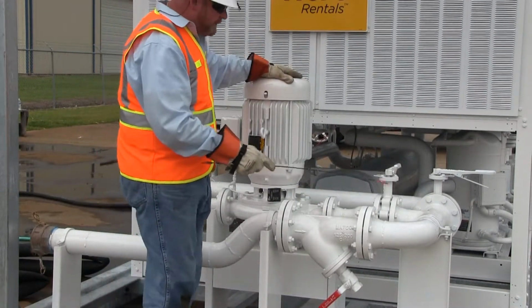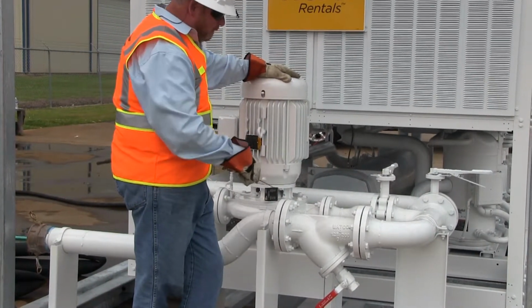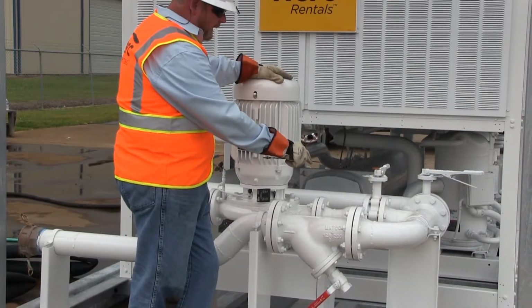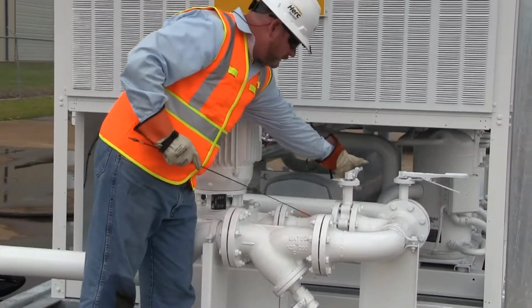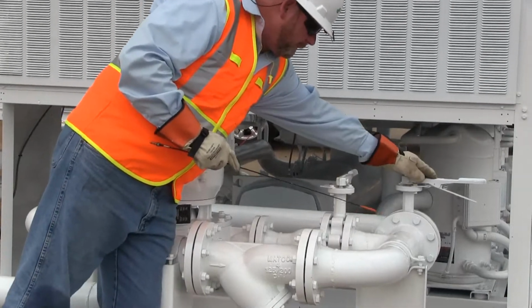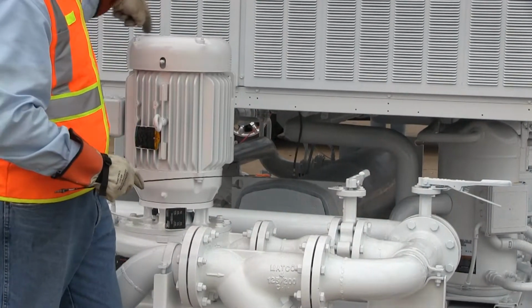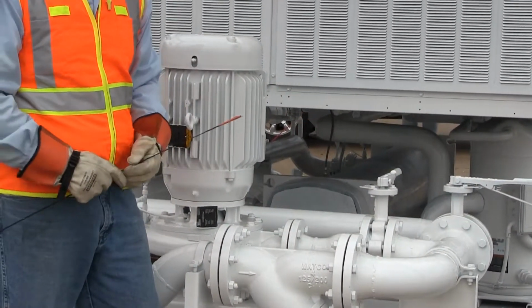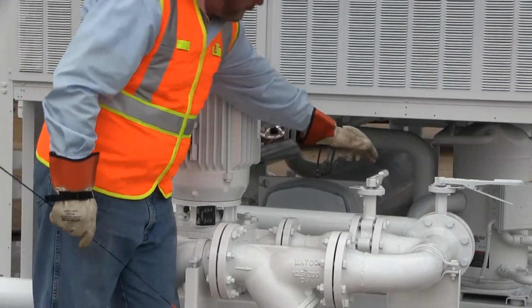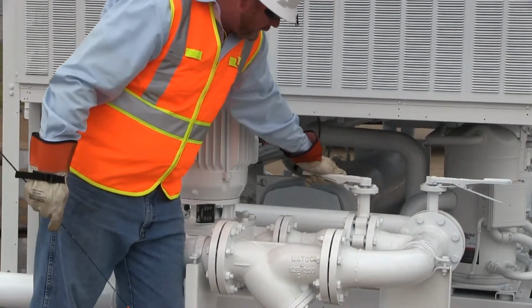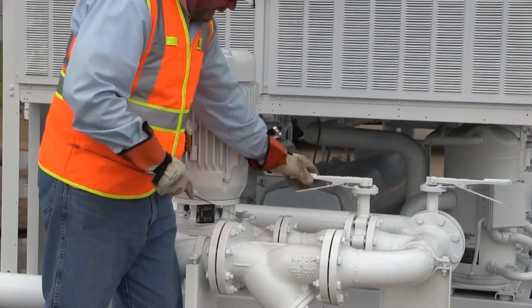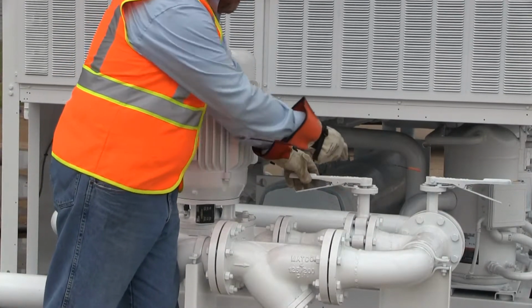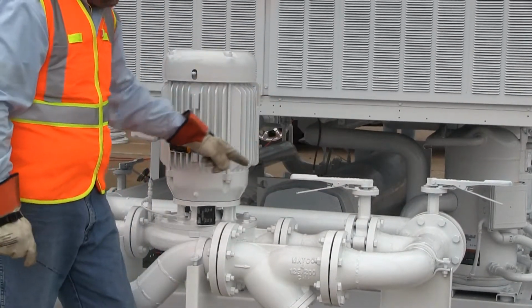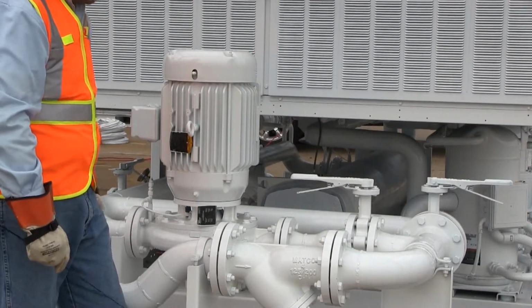Then you have a choice of either using our onboard pump here or locking it out by closing this valve, which is closed now here, and opening the bypass valve there to bypass the pump. That's if you're going to use the customer's pump. In this application, we're going to use ours, so we're simply just going to open the butterfly valve up. That opens up our path here. Our bypass valve is closed, so now we've formed our loop going back to our exchanger.